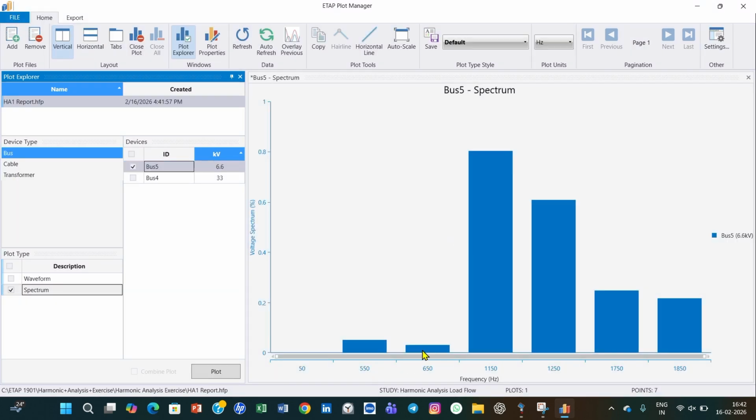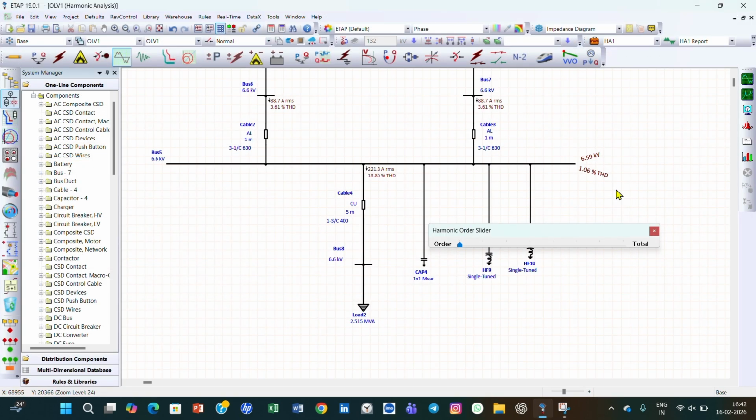We can see that both the 13th and 11th harmonics have been reduced. Now the 23rd harmonic is dominant, but mainly the client wants the 11th and 13th harmonics removed. You have to discuss with the client which harmonics you want to suppress. If we want to suppress the 23rd harmonic also, then you have to design a filter in the same way for that also. And you have the IEC guidelines also. If this harmonic is within the limits, then there is no need to design the filter.